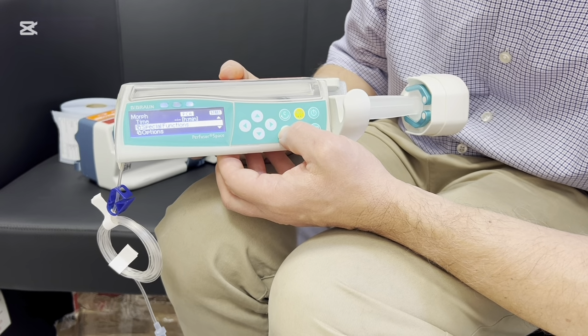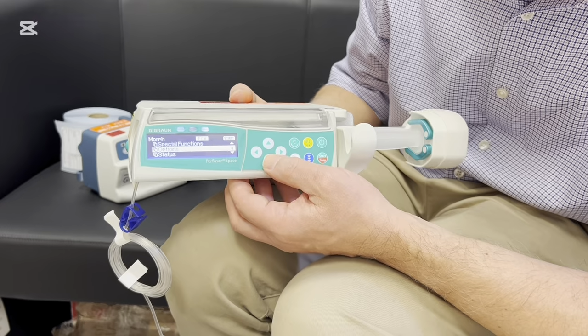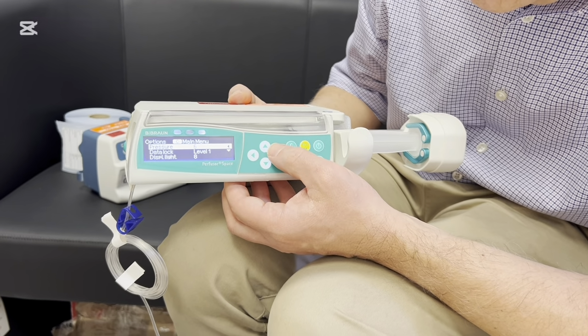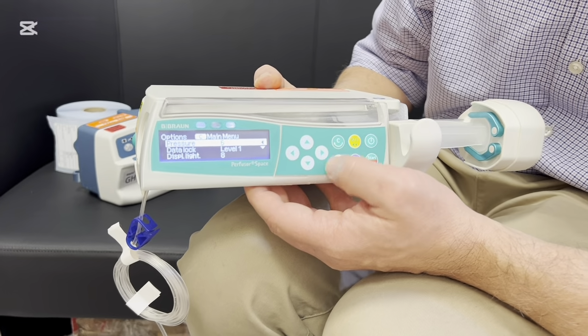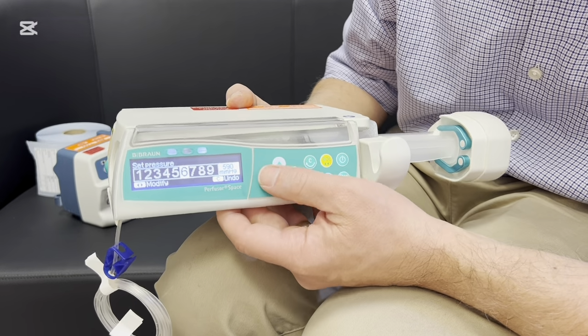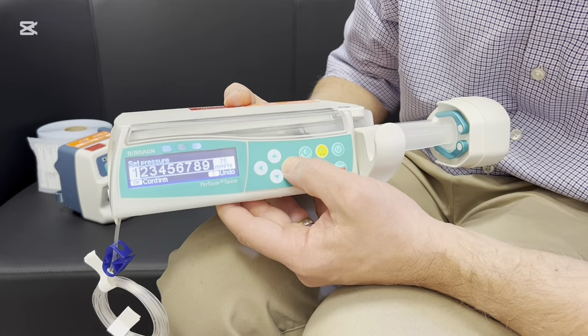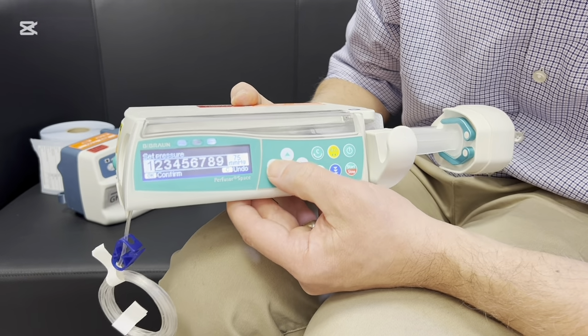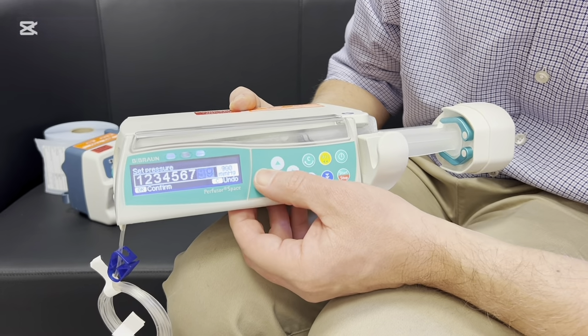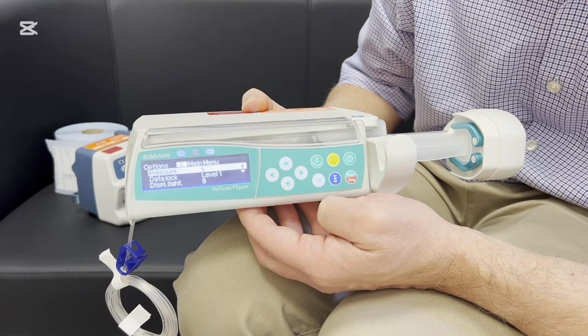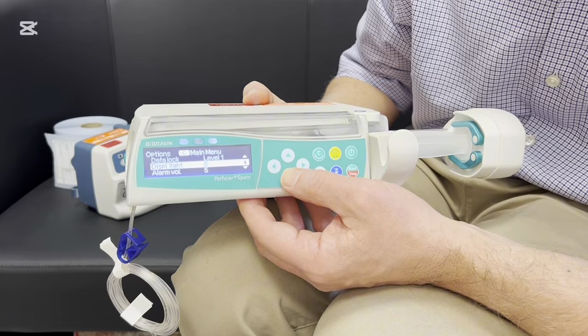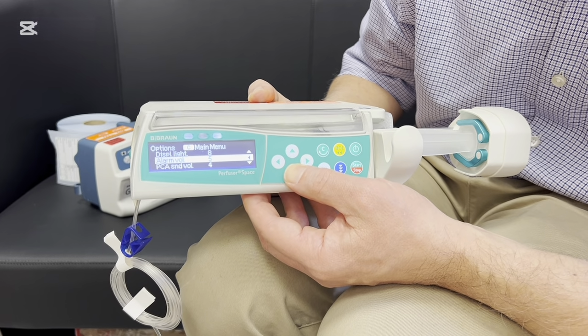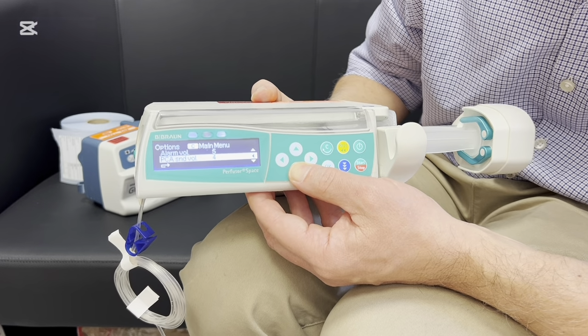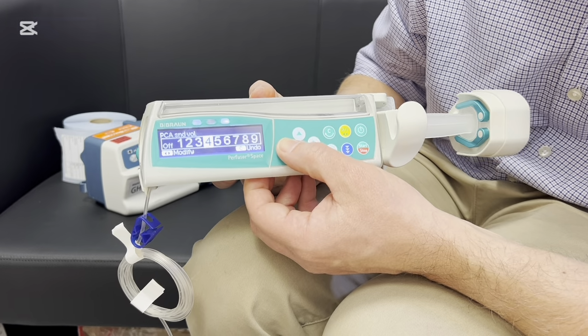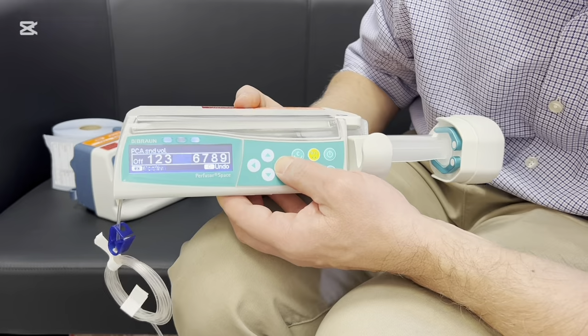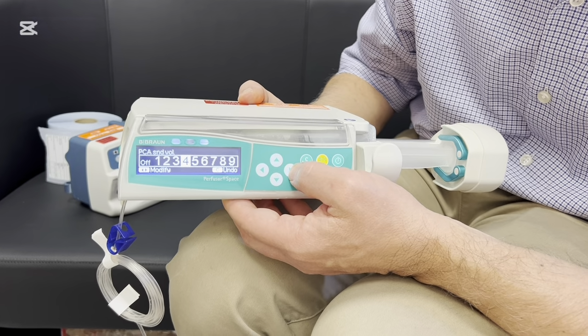So you may get called because the patient's experiencing failure to deliver the drug. So we'll go onto the options menu, press OK, and you can change the pressure that it allows you to deliver. It goes from 1 to 9, so from 75 millimeters of mercury all the way up to 900 millimeters of mercury. So we'll select something in the middle, sort of 6-ish. Press OK to confirm. The only other things you can change are going to be the display intensity and the alarm volume. Other than that, not a lot else. That's the volume when they press the button.